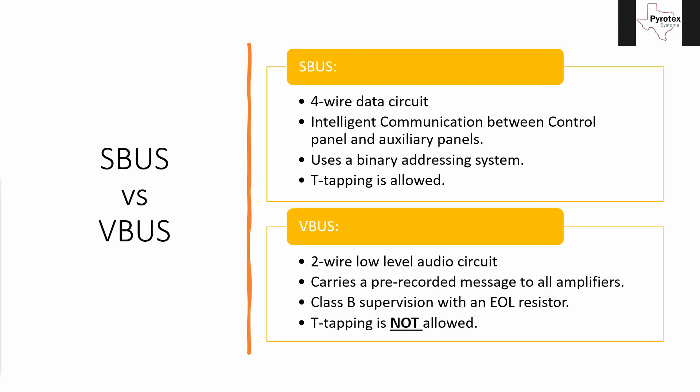If you're on a job site with a fire alarm control panel, a remote microphone at your annunciator, and a couple of amplifiers, when you pull your VBUS you have to hit your microphone first. The VBUS message only travels toward the end-of-line resistor — it doesn't travel backwards. So if you go panel, amplifier, microphone, amplifier, and then page from that microphone, only the last amplifier will get the message. You start at your fire alarm control panel, pull your wire to your microphone, then pull to all the amplifiers in the building. That's required because of the Class B supervision with the end-of-line resistor.